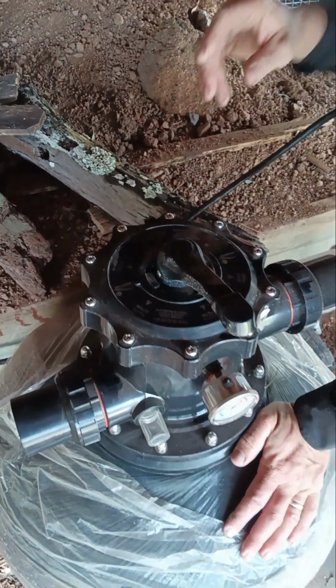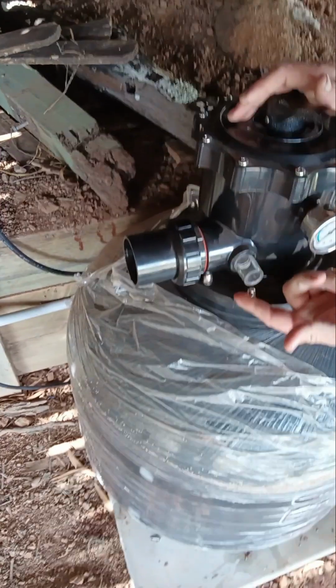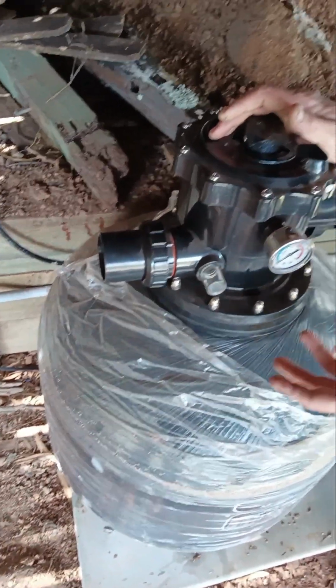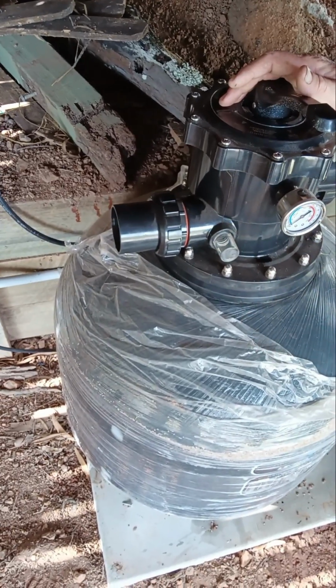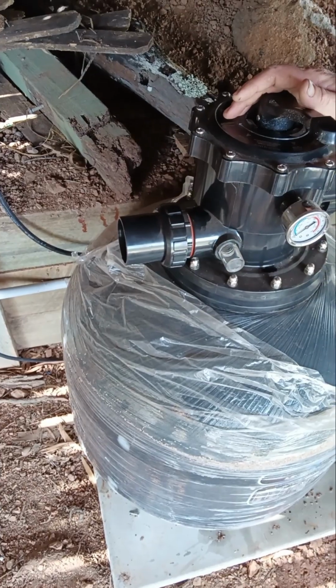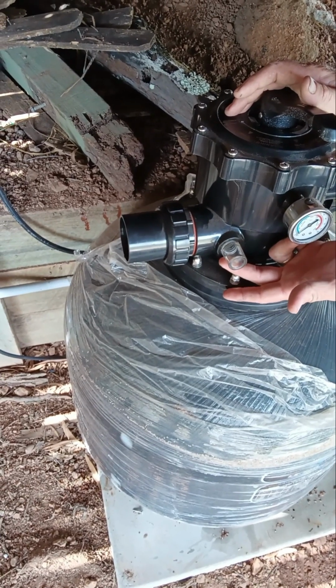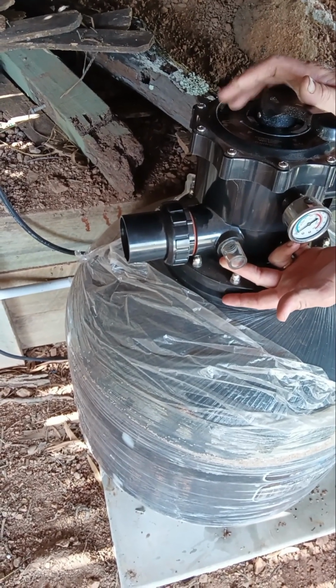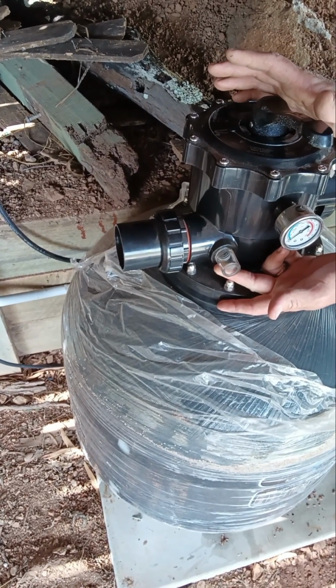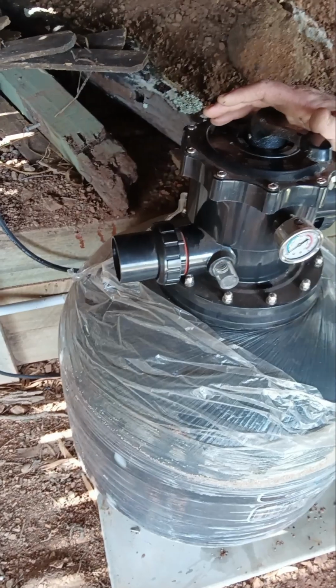What we have, forgive me, right here is your sight glass. So what's going to happen, the water's going to come through nice and clean. After about 3 to 4 seconds, you'll notice it go a dirty brown color. It's all the foreign contaminants. So I put my finger under the sight glass and I run for about 30 to 40 seconds, up to a minute, depending on how dirty it is, and then just run till crystal clear.